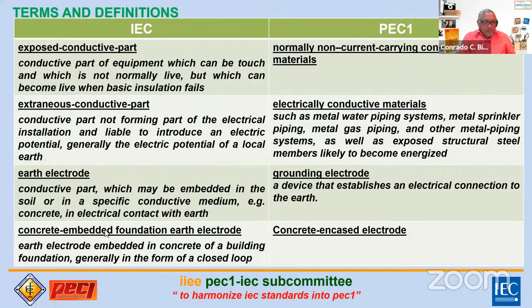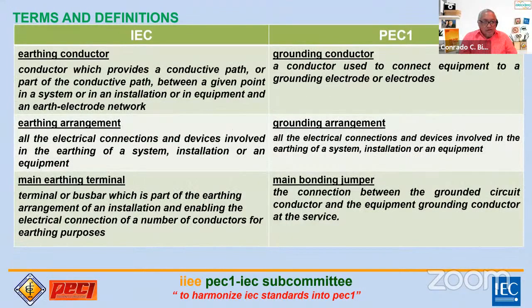Okay? And we have another one here, concrete embedded foundation earth electrode. Meron dito concrete encased electrode sa PEC. Okay, so these are the terminologies, meron pang iba rito. We have called earthing conductor, and in PEC we have the grounding conductor. A conductor which provides a conductive path between a given point in a system or in an installation or in equipment and an earth electrode network. Okay, grounding conductor, a conductor used to connect equipment to a grounding electrode or electrodes. So ito na yon, yung sa source mo, halimbawa meron kang neutral, connect mo sa earth o sa ground. So meron kang conductor between the electrode saka yung sa system neutral mo. So these are called the grounding conductor.